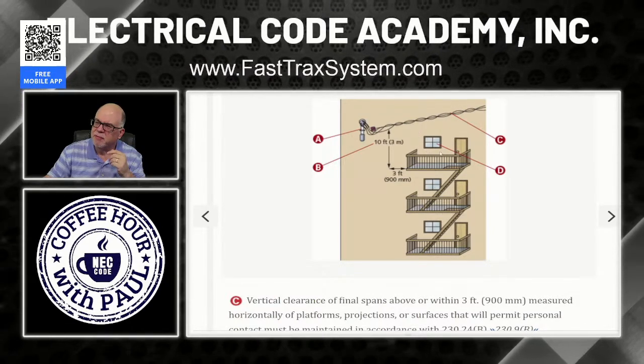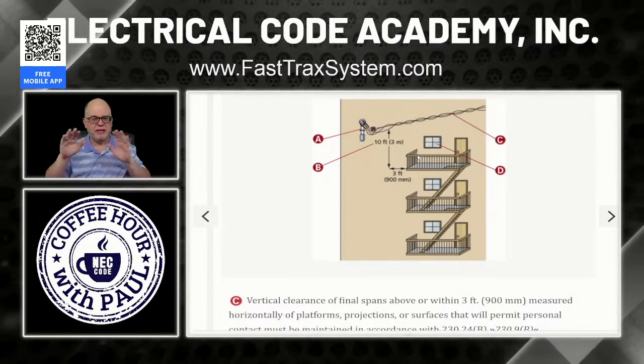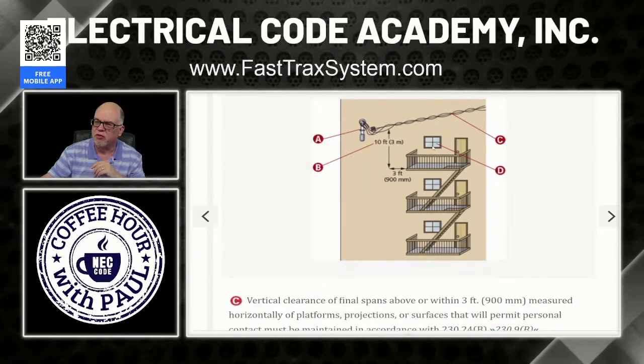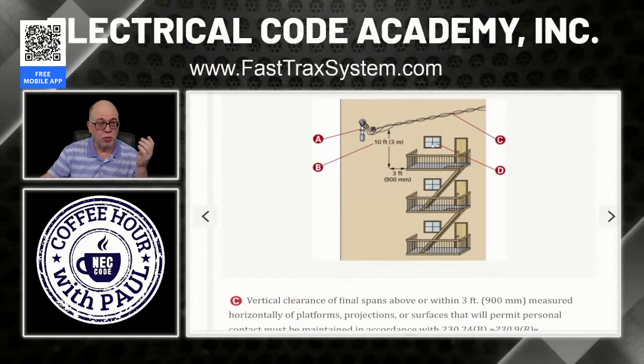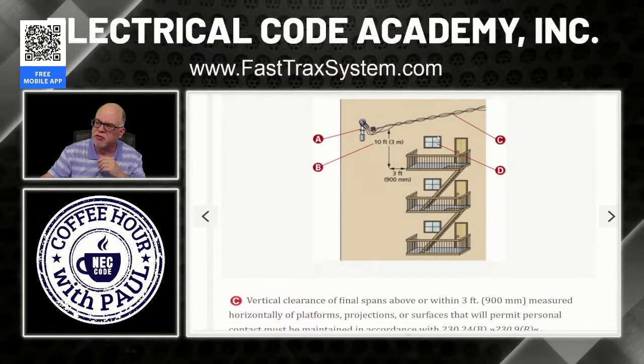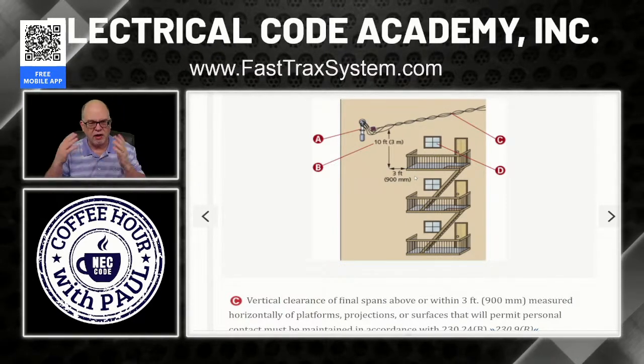So this platform, I have to have the clearance above it, right? But I also have to make sure that these conductors stay 3 feet away from it. So all of that, here's a door, gets to be 3 feet away from the door. Here's a window. We'll assume this is an openable window. Okay, stay 3 feet away from it. Of course, this is over the window, so that's not an issue. Okay, so we still have all these clearances that we have to be aware of, okay?